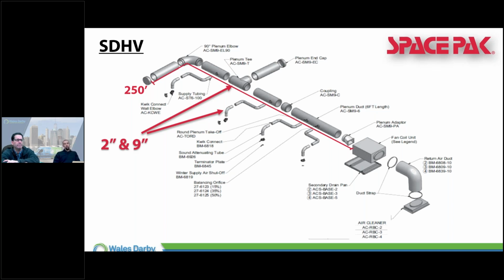So that's our plenum pretty much. And then when we talk about those outlets, I have 7 outlets per ton up there. We might see some slides at 6 outlets per ton. I always like to make sure we're covering our bases, but with 7 outlets per ton, it's pretty easy to at least get a general idea on how the system's going to go together.